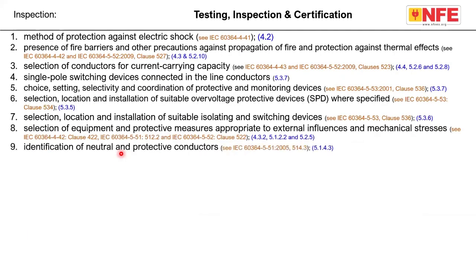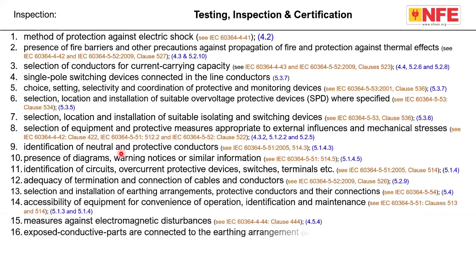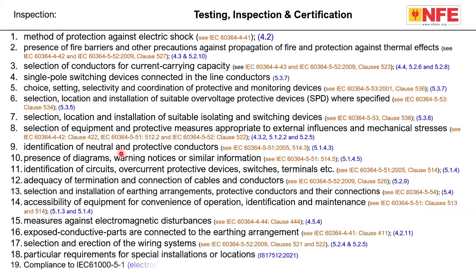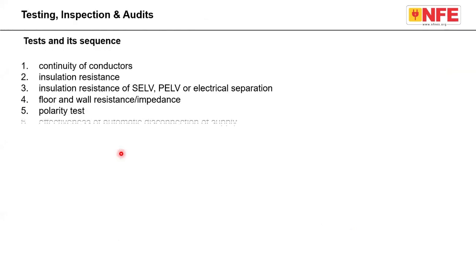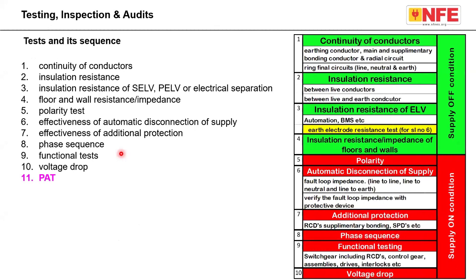Similarly, we will educate the biomedical engineer about the requirement of inspection and testing. Inspection means there is not one parameter, there are so many parameters which need to be inspected, and each parameter is governed by some clauses of the National Electrical Code. And finally, we are supposed to make a test. We will educate the biomedical engineer how he can carry out the test, starting from continuity up to the last. PAT stands for portable appliance test. We will give you solutions.